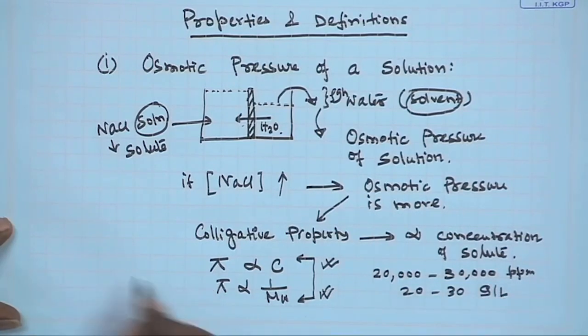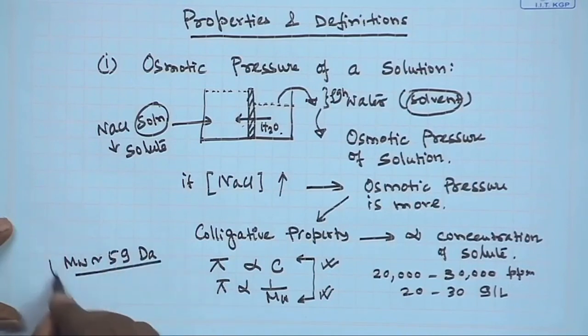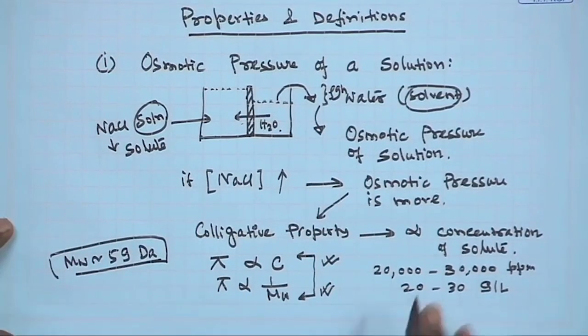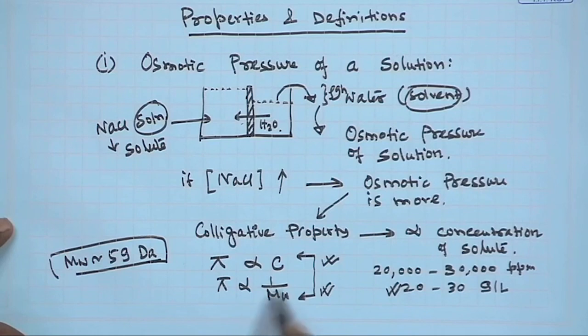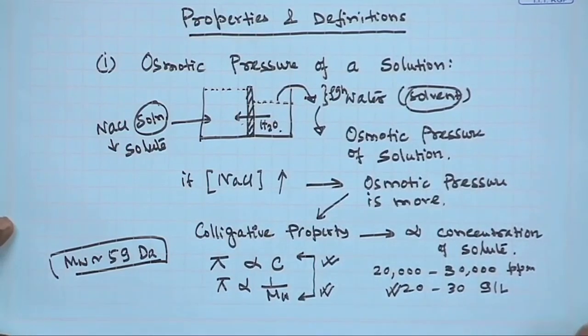The molecular weight of NaCl is around 58.5 daltons. At sea water concentrations of salt with this low molecular weight, the osmotic pressure turns out to be around 20 to 22 atmospheres. Therefore, in order to get reasonable throughput, one must operate above the osmotic pressure. This is why an operating pressure of 25 atmospheres or more is prescribed for reverse osmosis systems.